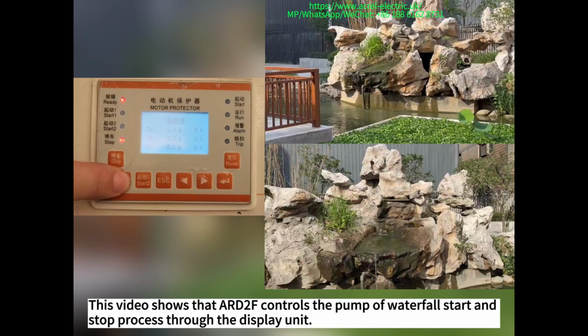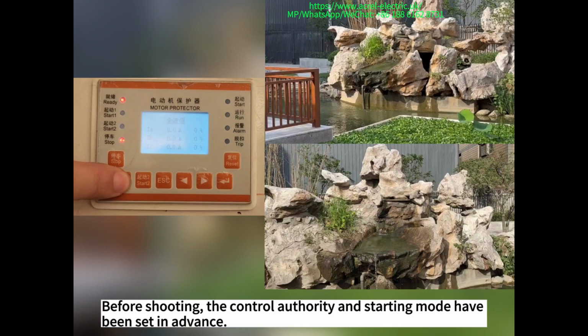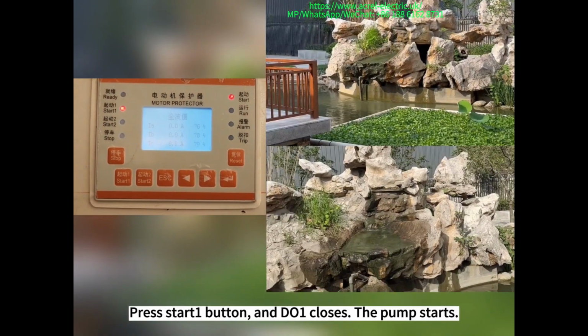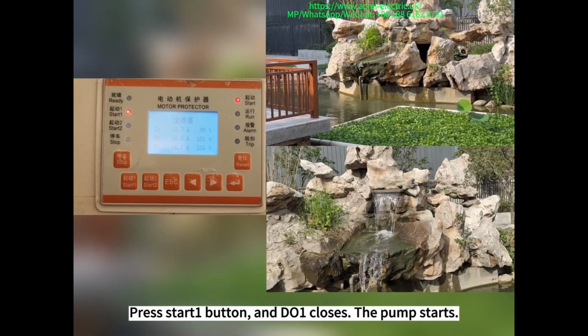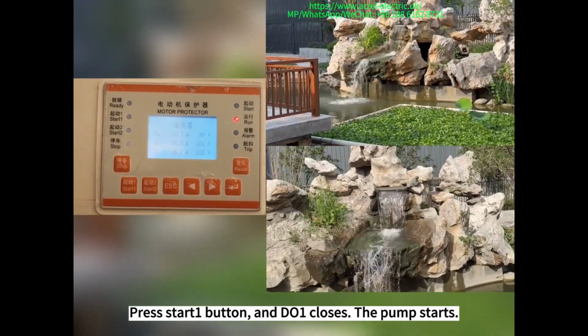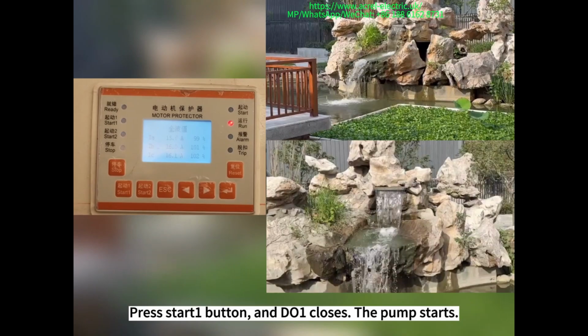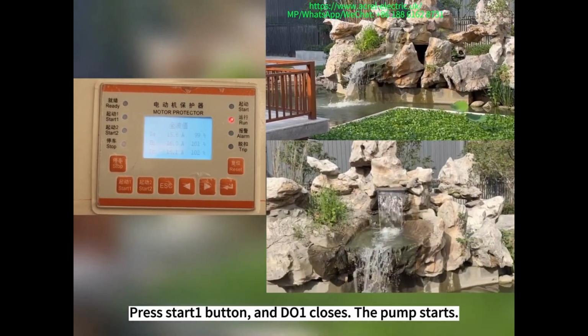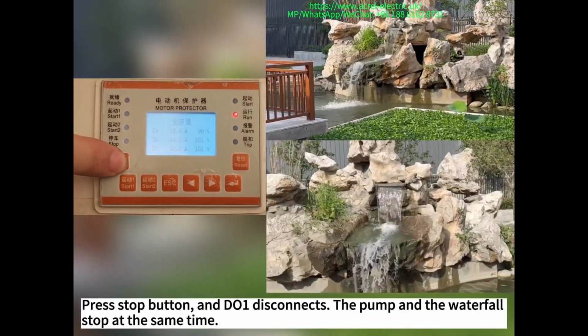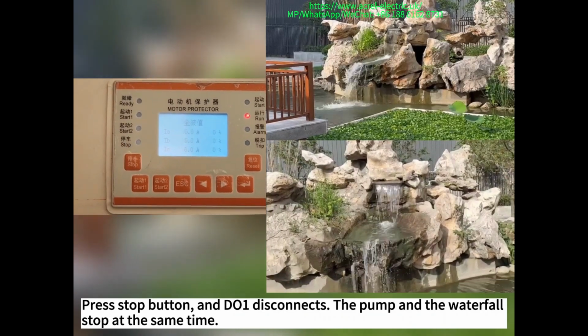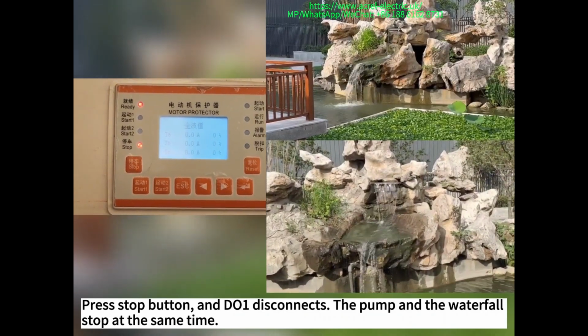This video shows that ARD2F controls the pump of waterfall, start and stop process through the display unit. Before shooting, the control authority and starting mode have been set in advance. Press Start 1 button, and DO1 closes. The pump starts. Press Stop button, and DO1 disconnects. The pump and the waterfall stop at the same time.